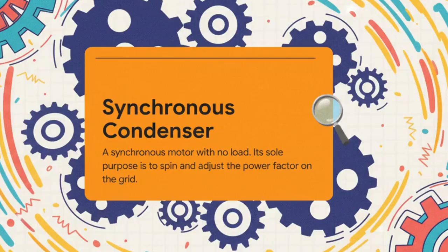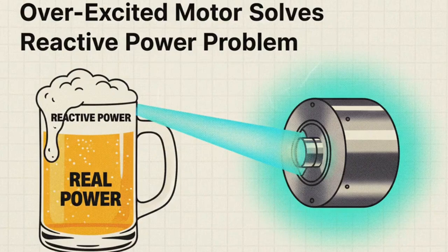And the solution? Well, it's one of the absolute weirdest machines in all of electrical engineering, the synchronous condenser. Okay, get this. It is a massive synchronous motor that isn't connected to anything. It does zero mechanical work. Its only job is to spin. So why on earth does this thing exist? Here is the brilliant part. Remember how a synchronous motor needs its own DC power to get excited? Well, if you overexcite it, basically you give it more DC current than it needs just to spin, it starts acting like a generator. But instead of producing real power, it starts producing the exact kind of reactive power that all those other induction motors are gobbling up.